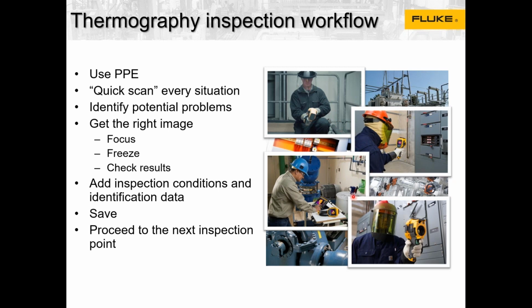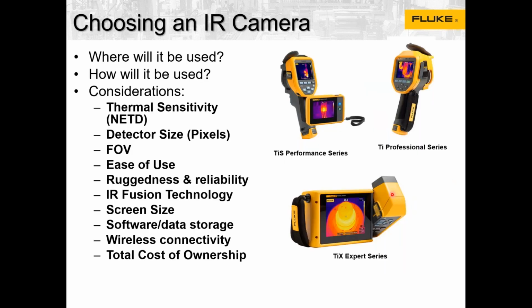For this, it means you need to choose the right camera for your application. To choose the right camera, you need to ask two questions: where will it be used, and how will it be used. So you can see for Fluke, we have a wide range of thermal imagers. I will go through the range of the thermal imagers after that. But also you need to take into consideration the thermal sensitivity, the detector size, the number of pixels, which is very important, because each pixel is a point of temperature. The FOV, or field of view, is also very important. You need to have a camera which is easy to use, rugged and reliable if you are using it in a rough area. Most of our cameras are drop tested for 2 meters.